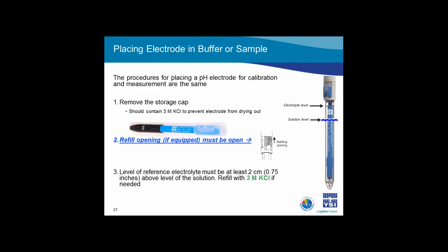When placing a sensor in either a buffer for calibration or a sample for measurement, make sure you first remove the storage cap from the tip of the sensor. The storage cap is provided for storing the electrode during shipment and long-term storage. I consider anything 3 weeks or longer to be long-term storage. For field probes, we'll talk about storage of lab probes shortly.